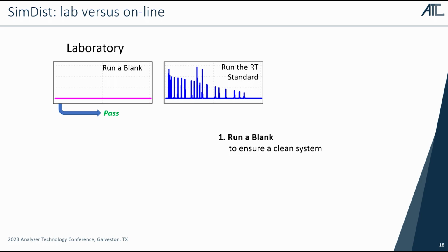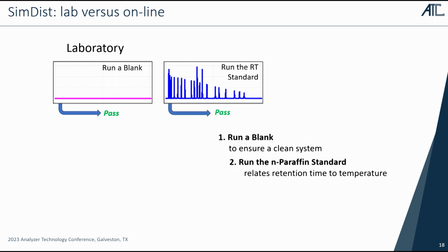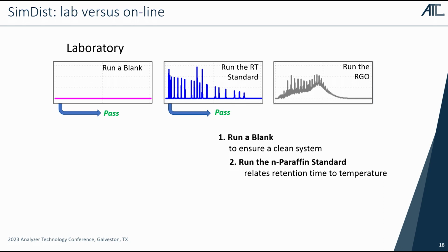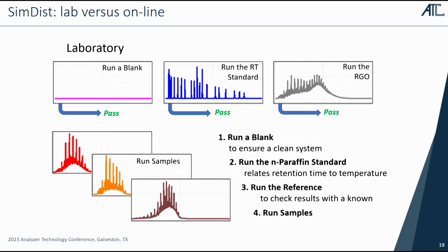It's a series of N-paraffins. We happen to know their boiling point temperatures, so we use that information to convert the x-axis from retention time to temperature. Then, if that works, we take a reference gas oil and run that through the system. The reason we do that is we want to check with a known quantity to make sure that the boiling point distribution is within the range that we accept. This is the ASTM procedure. This is fine. And then we can run samples.